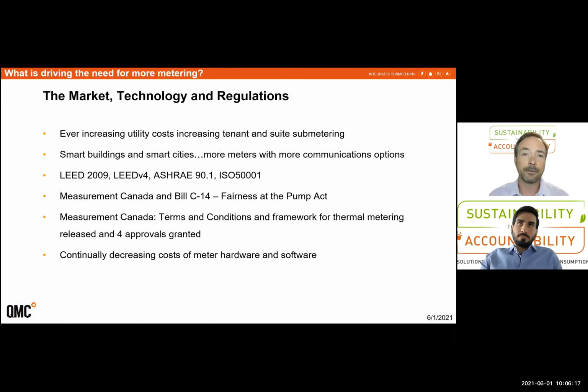One of the first big ones we started working with was LEED 2009, LEED version 4, ASHRAE 90.1, and the energy standards set out in that are really enforcing a lot of metering within Canada these days. It's probably the standard we see the most being utilized, and even ISO 50001. And on the regulatory side, we have Measurement Canada that, with the Fairness at the Pump Act, is highly regulated electrical and gas metering. And very recently, Measurement Canada has begun regulating thermal or BTU energy metering. And we'll talk a bit more about that in the discussion today.